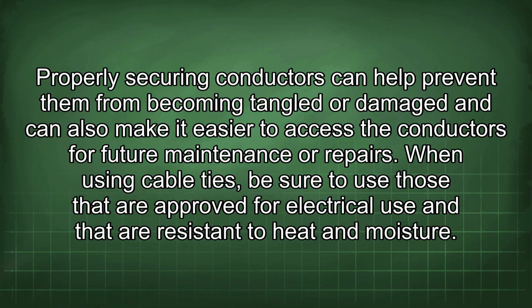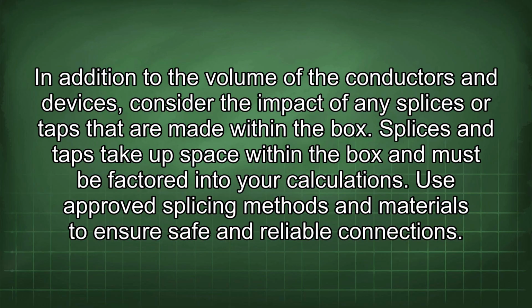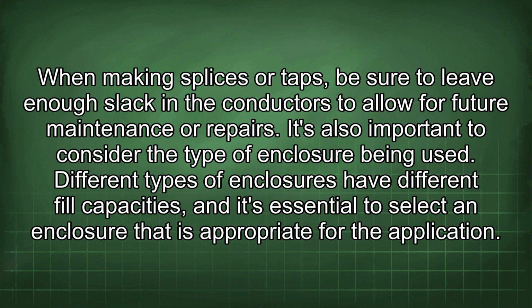In addition to the volume of the conductors and devices, consider the impact of any splices or taps made within the box. Splices and taps take up space within the box and must be factored into your calculations. Use approved splicing methods and materials to ensure safe and reliable connections. When making splices or taps, be sure to leave enough slack in the conductors to allow for future maintenance or repairs.